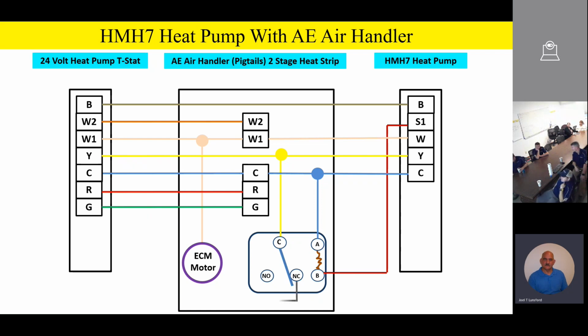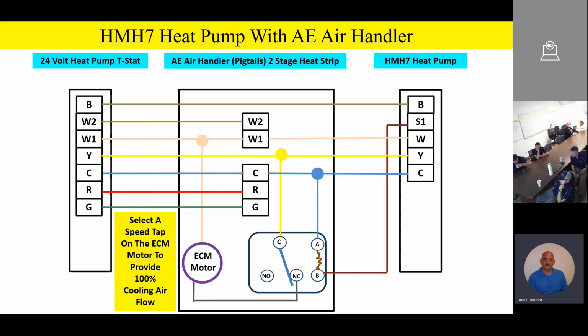Now watch this. On the normally closed contact on the relay, going over to the motor, you're going to select the airflow speed tap to give you 100% cooling airflow. Now team, this is important because you'll notice that with the relay just sitting there unenergized, anytime we get a call for compressor operation outside, the way this relay is wired up right now, it's going to drive the fan to your 100% cooling airflow. Any questions or comments so far? Good? Okay. All right, so the relay right now, as it's configured, just sitting there and not energized, we're going to have 100% cooling airflow on the ECM motor.